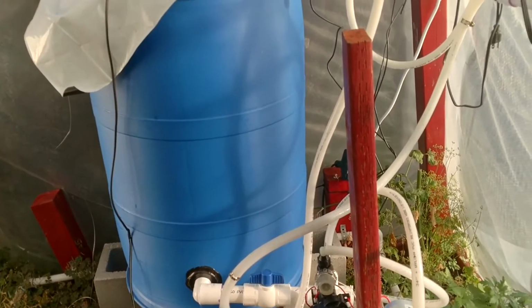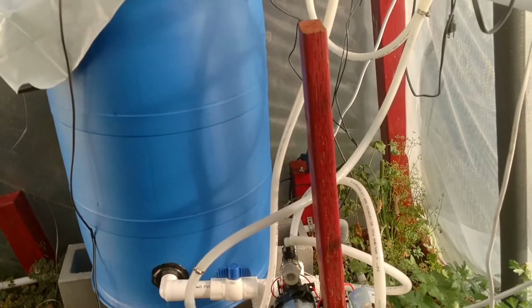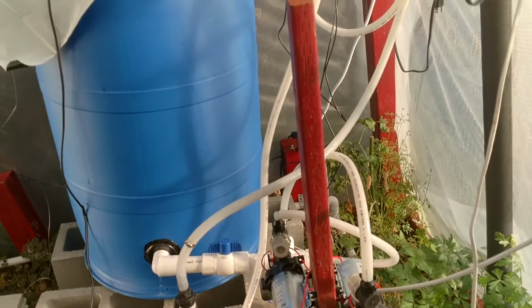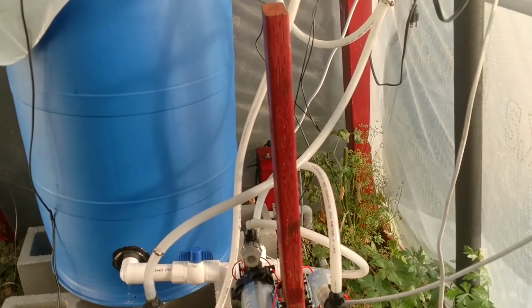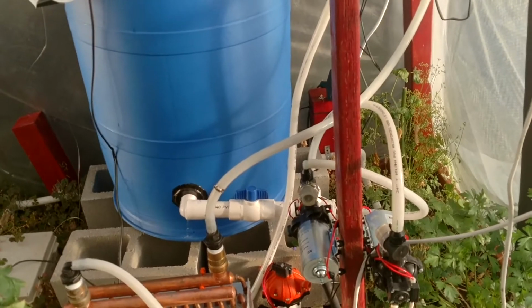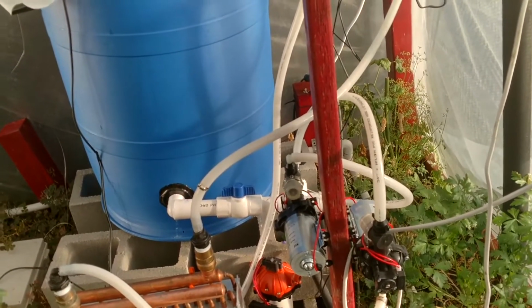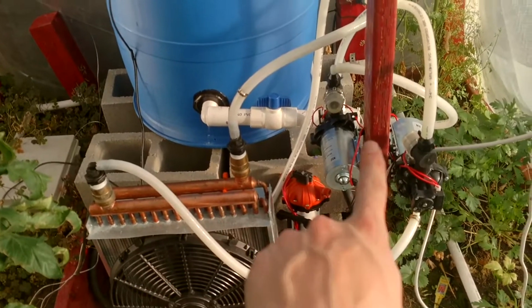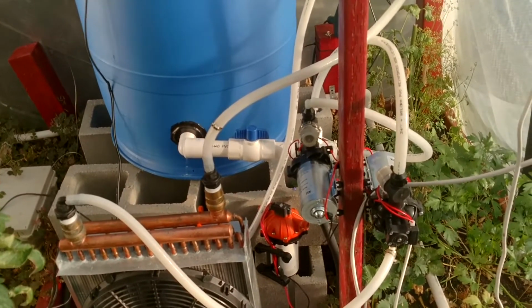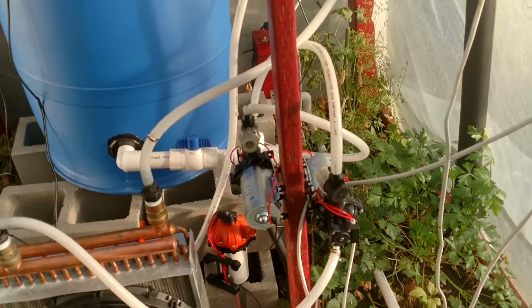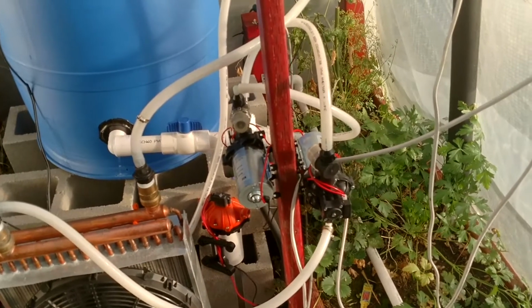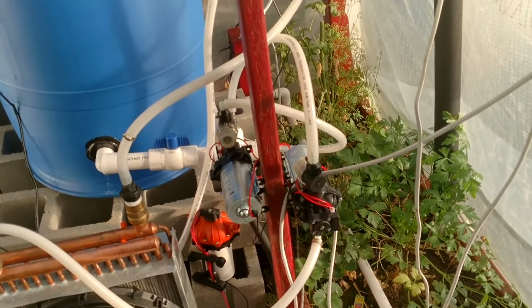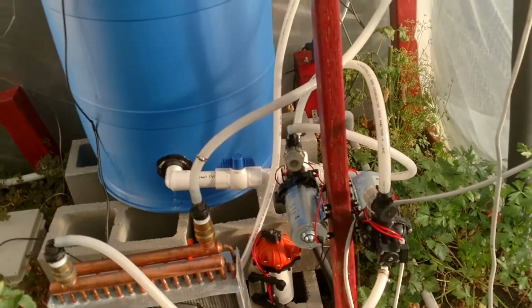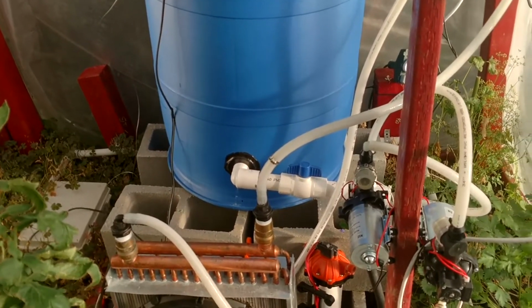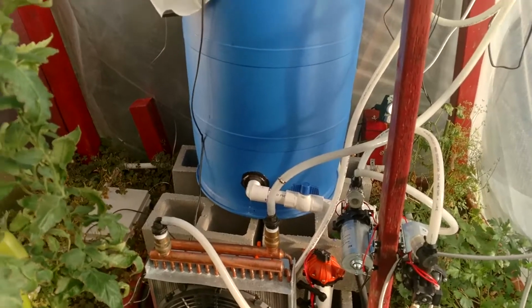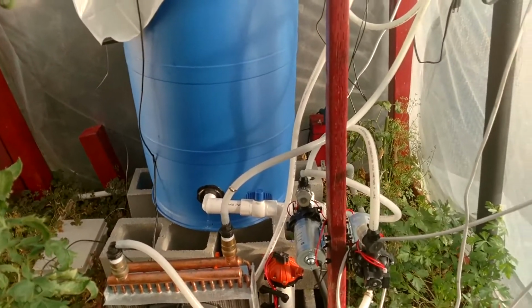It's very efficient to run the pumps during the night - it's cheap, and I can turn them off depending on how cool my water is. I could go from about 400 watts with all three systems running, the fans and pumps, down to just 50 watts when only the chiller's running. The chiller runs very efficiently at nighttime, and geothermal is free energy from the earth, so far it's worked very well.